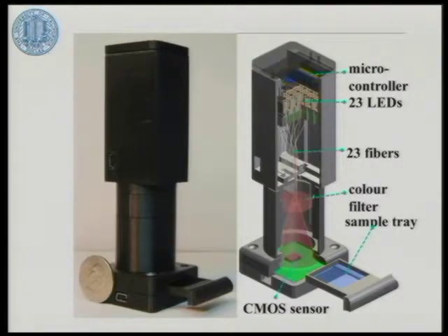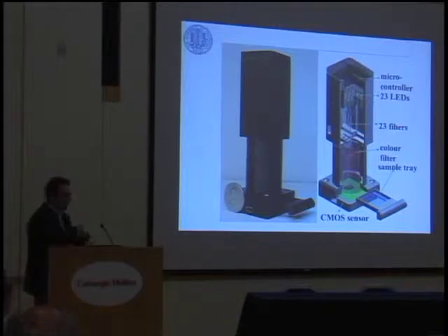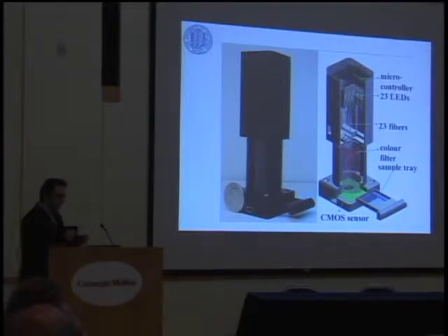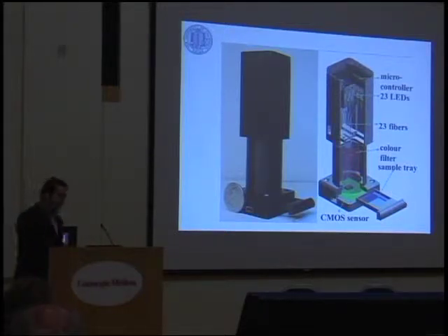we've done is, instead of using a single light-emitting diode, LED, we put here some 20 of them. It's still cost-effective in terms of telemedicine and global health because an LED is pretty inexpensive, on the order of $0.2 per piece. Then we have the microcontroller here, which turns on these LEDs one by one. So at a given time, the sample that you insert from the side, which is very close to the CMOS imager, will be illuminated by a single LED, which changes its position based on the microcontroller input.